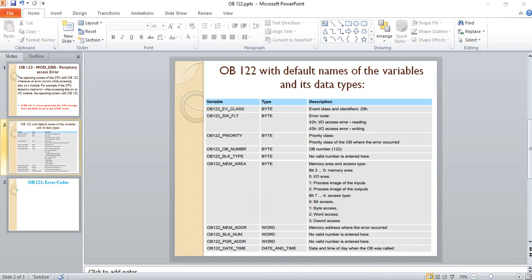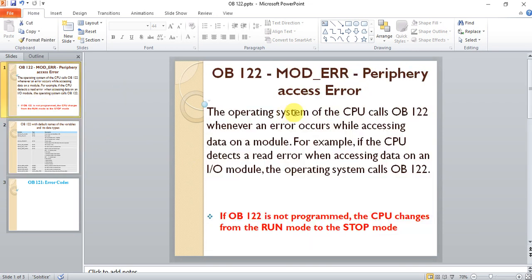Hello again. I came with another video about organization blocks used for troubleshooting. We will see OB122 in this video. OB122 is a peripheral access error or module access error. The operating system of the CPU calls OB122 whenever an error occurs while accessing data on a module.